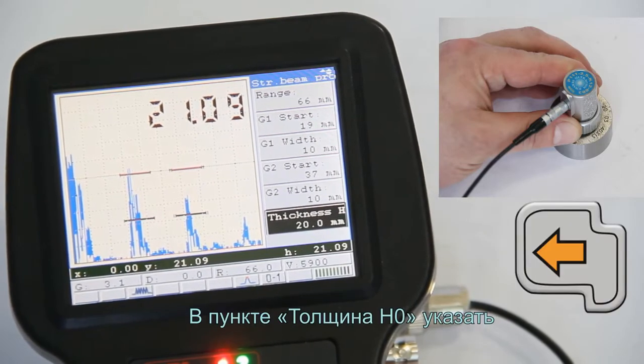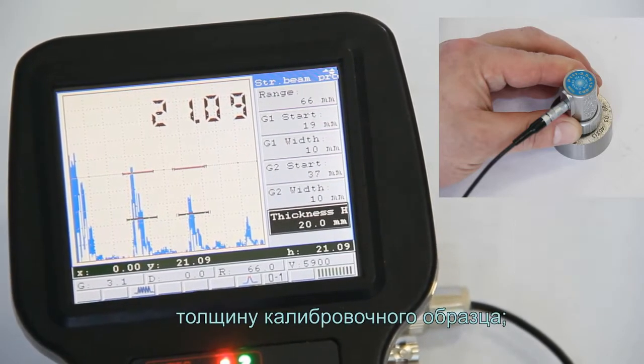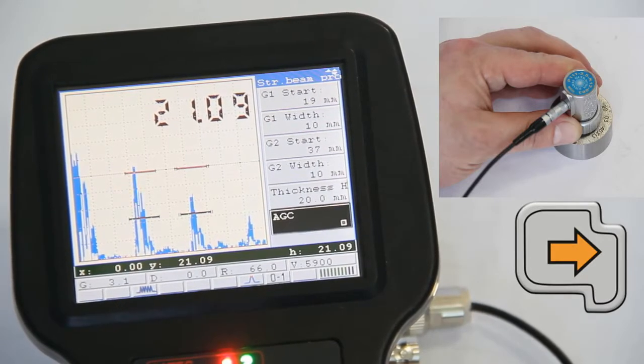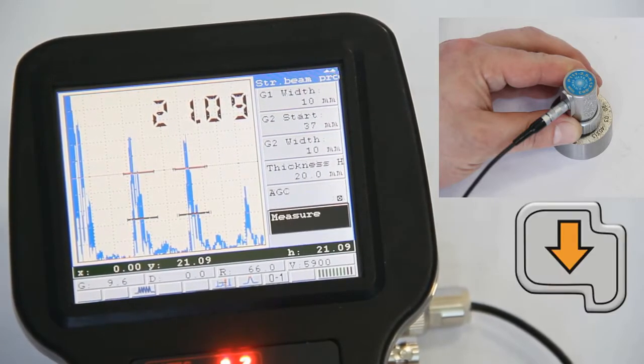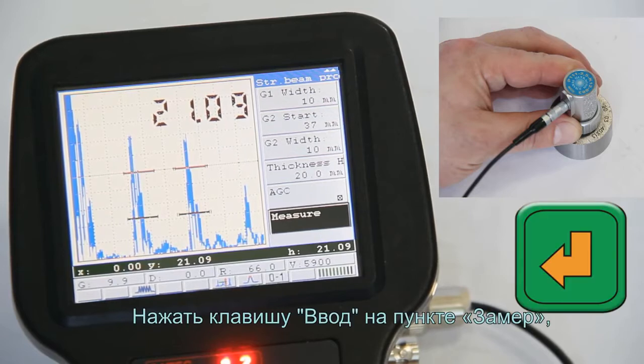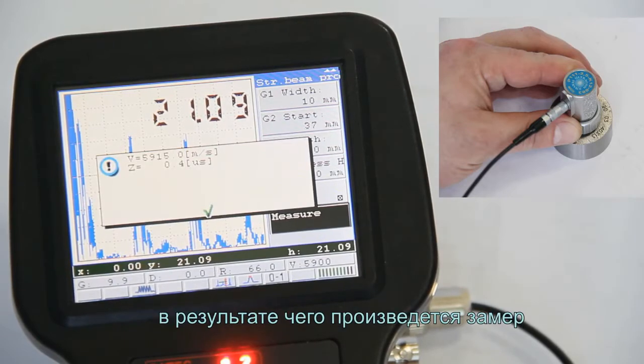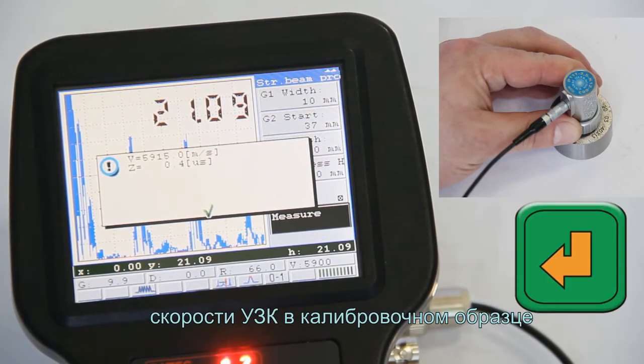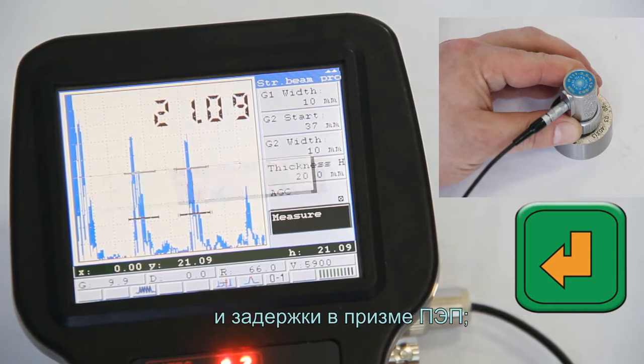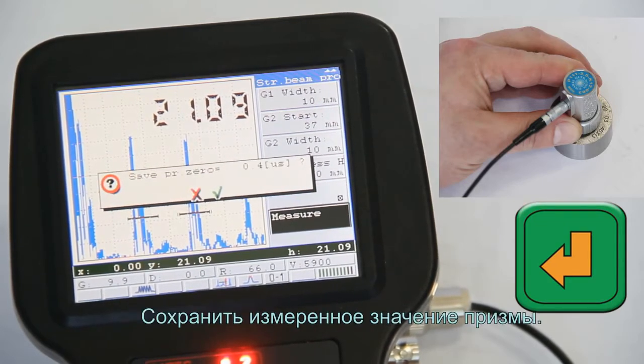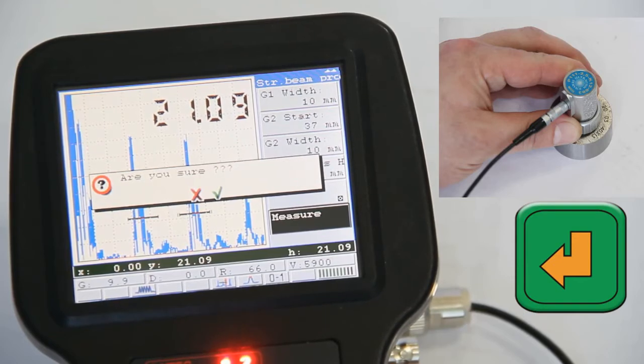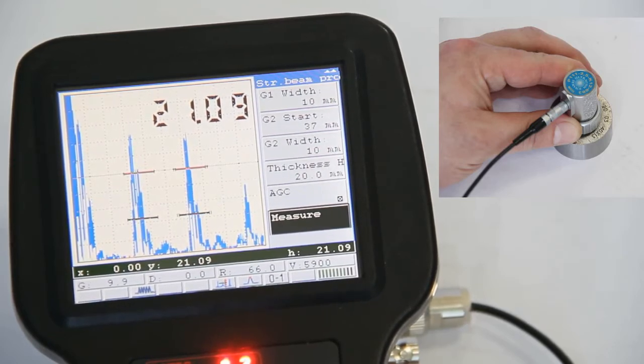In the thickness H item, indicate the thickness of the calibration block. Activate the AGC mode. Press the Enter button in the Measure item. As a result, the measurement of sound velocity is carried out in the calibration block, and the delay in probe 0. Save the measured probe 0 value.